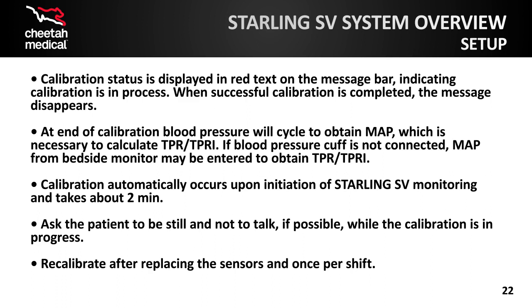At the end of calibration, manually enter the MAP from the A-line or bedside monitor to obtain TPR and TPRI if you are not using the Cheetah Starling SV NIBP cuff. Note that the system needs to be recalibrated after replacing sensors. To ensure optimal operation, check sensor placement and time of sensor placement at the beginning of each shift and recalibrate. Check sensor placement and time of sensor placement when hemodynamic numbers are in question and recalibrate.